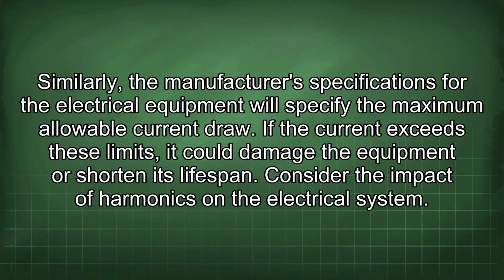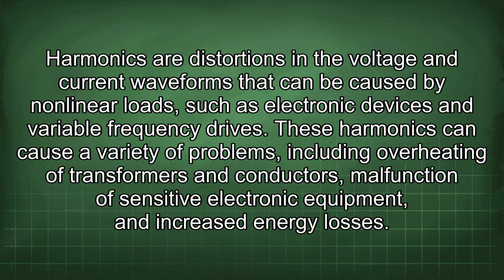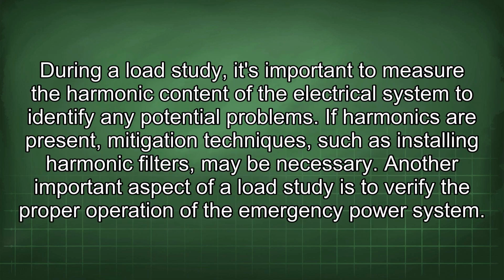Consider the impact of harmonics on the electrical system. Harmonics are distortions in the voltage and current waveforms that can be caused by nonlinear loads such as electronic devices and variable frequency drives. These harmonics can cause a variety of problems, including overheating of transformers and conductors, malfunction of sensitive electronic equipment, and increased energy losses. During a load study, it's important to measure the harmonic content of the electrical system to identify any potential problems. If harmonics are present, mitigation techniques such as installing harmonic filters may be necessary.